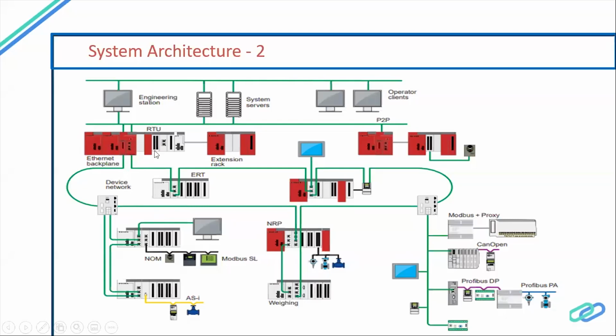So this is your backplane with the PLC controller, and this is the extension rack. If required, you can extend the slots; PLC racks may be available with 7 slots, 10 slots, or 12 slots. So if required, you can increase the IO. For that you need an extension rack, you need to connect the cable and add the rack, and add your IO as per your process requirement.